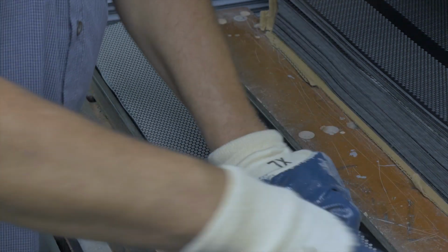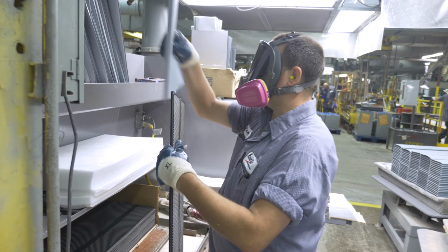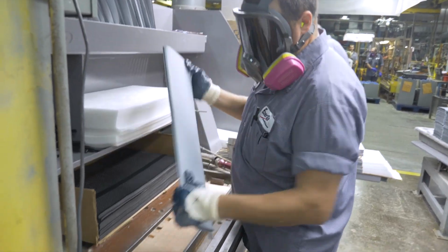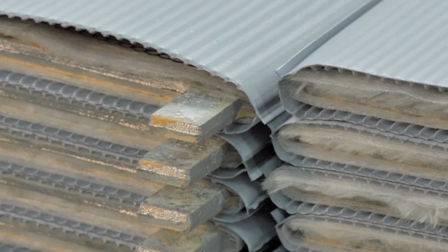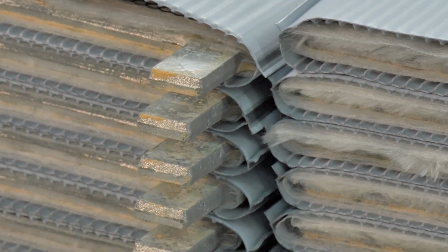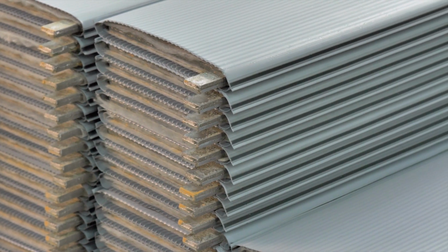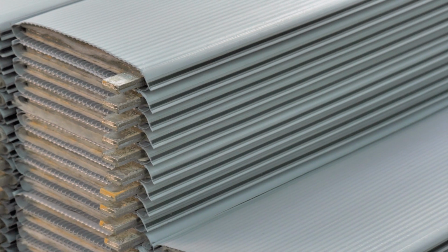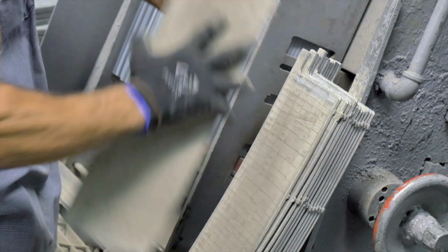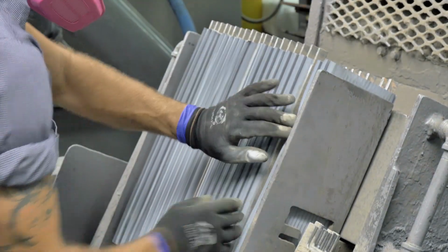Douglas Battery has overcome this failure mode by making separator sleeves that fit around each positive plate, so visual quality checks are sufficient to assure they are in place. In addition, these sleeves insulate the edges of the plates from edge shorts. The sleeves are welded ultrasonically and cut to the proper length. A test verifies the weld is stronger than the base material. The positive and negative plates are stacked together to form an element.